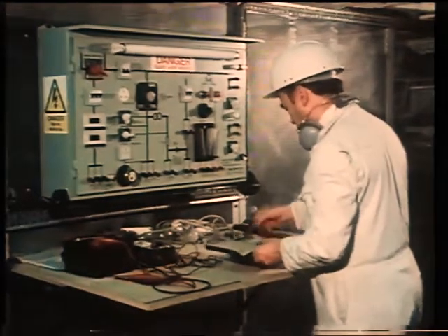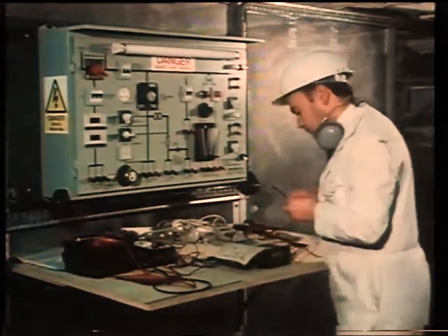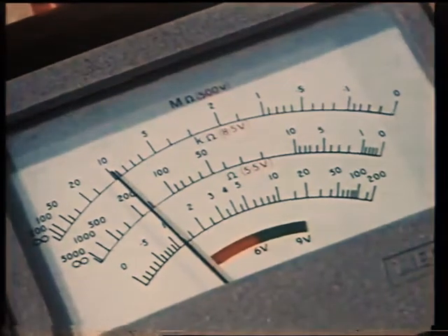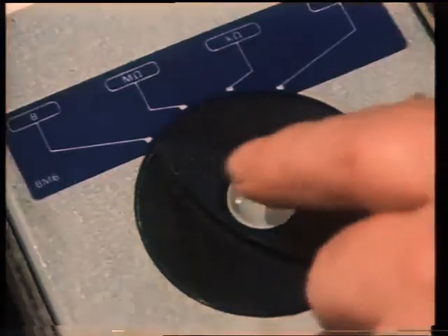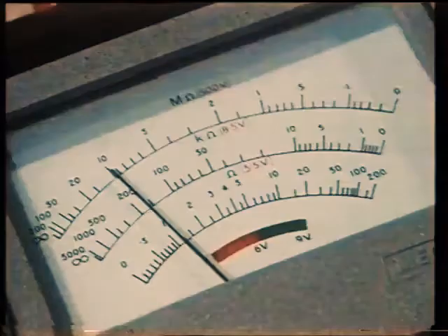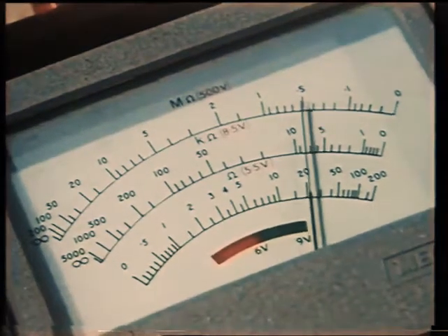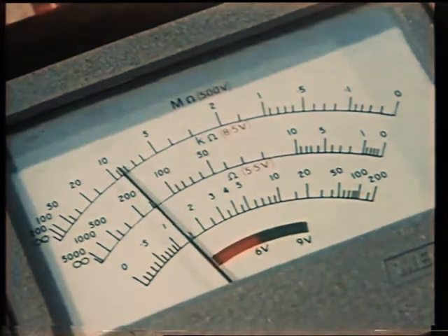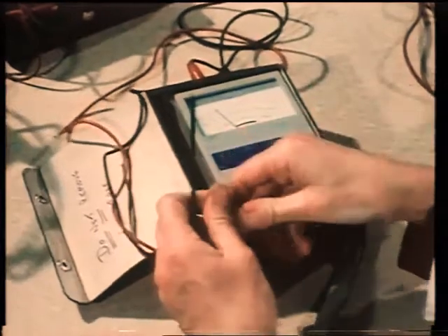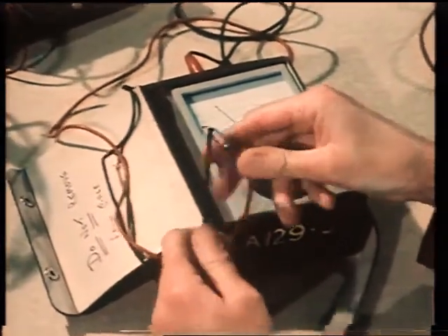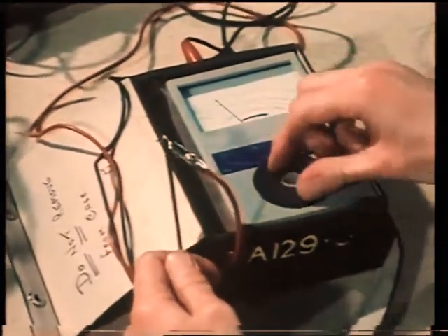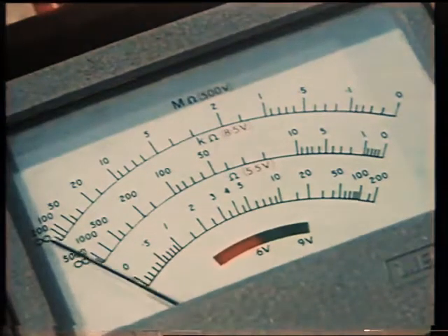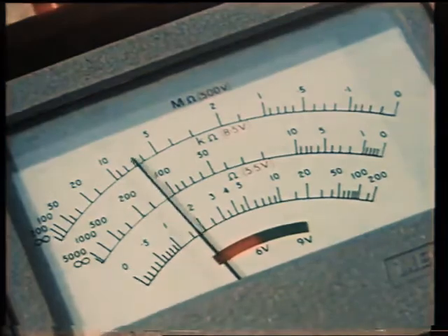An insulation resistance tester is used to monitor the condition of the electrical circuitry on board ship, as well as for fault tracing. On this particular model, there is a battery test as well as ohm, kilo-ohm, and megohm scales. The meter is tested on all its scales before use by connecting the probes together when the meter shows no resistance, or closed circuit, on all its scales.